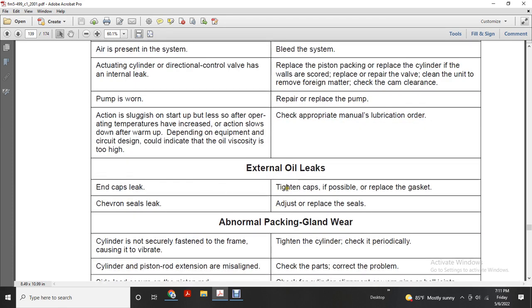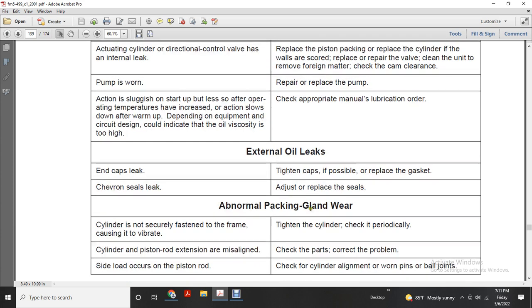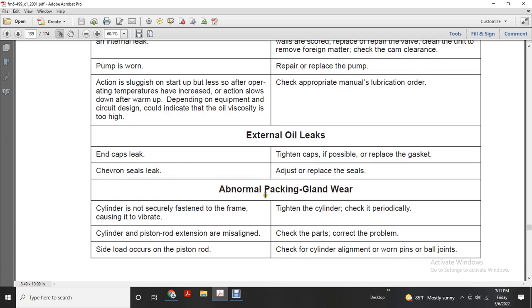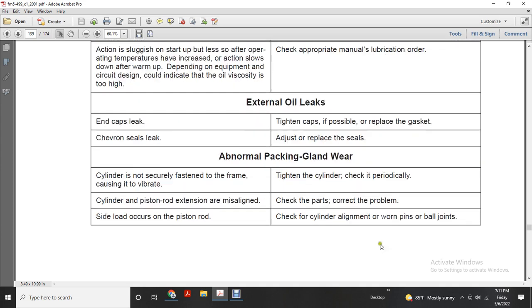External oil leaks. End cap leaks. Tighten caps if possible. Replace gasket. Basket or chevron seals leak: adjust or replace worn seals. Abnormal packing gland wear. Cylinder is not securely fastened in the frame, causing vibration: tighten the cylinder and check it periodically. Cylinder and piston rod extension are misaligned: check the parts and correct the problem. Side load occurs on the piston rod: check cylinder alignment and worn pins or ball joints.